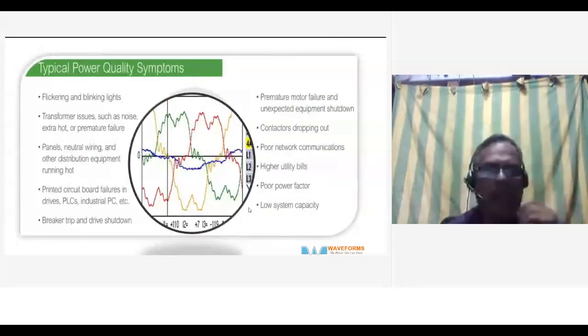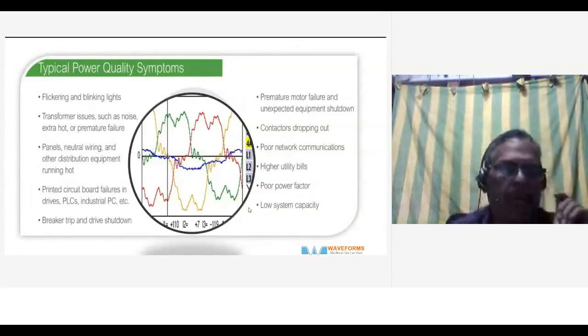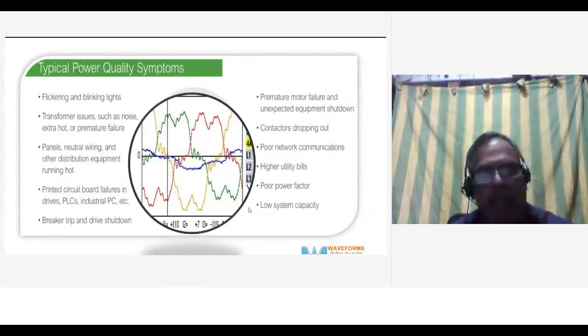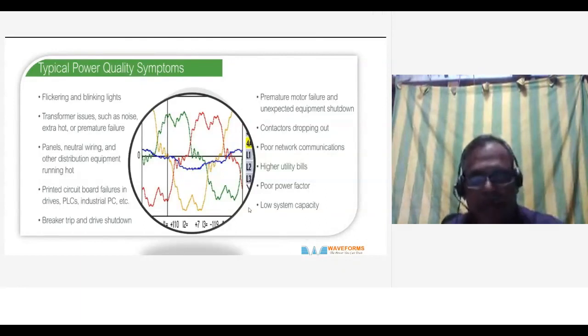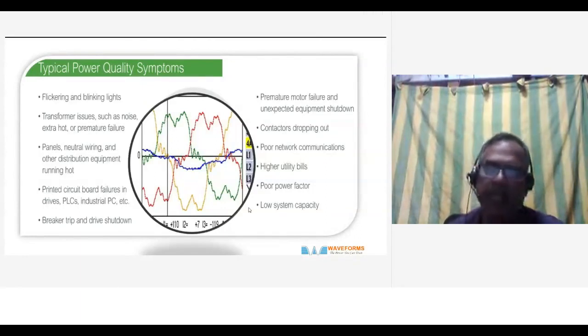You have these power quality issues: transformer issues such as noise, extra heat, premature failure; panel, neutral wiring, and other distribution equipment running hot; printed circuit failures; drives, PLCs, industrial PCs failing; breaker overheating and drive shutdown; premature motor failures; contactors stopping or poor network communications; high utility bills; poor power factor; and low system capacity.